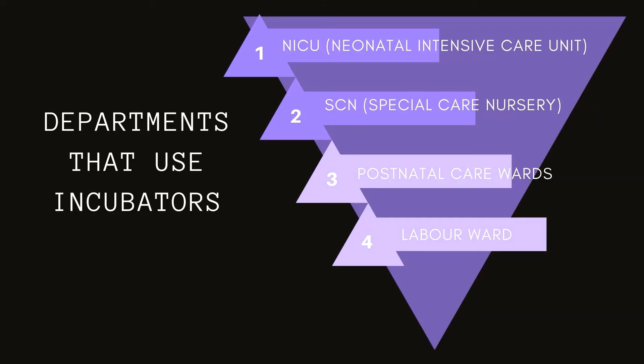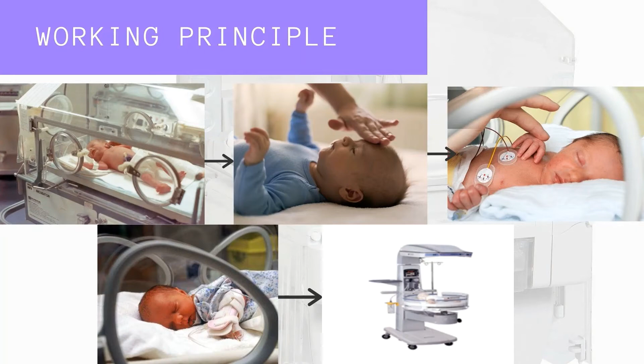Next is the working principle of an infant incubator. This is the basic illustration of an infant incubator. First, the mattress on which the baby lies is completely enclosed by a clear plastic canopy. Temperature and humidity are the parameters which have to be controlled. A temperature sensor is taped to the baby's skin, and the incubator heater adjusts to maintain the baby at a constant temperature. The isolation chamber helps to regulate the temperature of an infant and can provide air which is enriched in humidity and oxygen. Last, the temperature in the incubator is increased or decreased by a heating element which is placed below the mattress. So this is the basic working principle of an infant incubator.